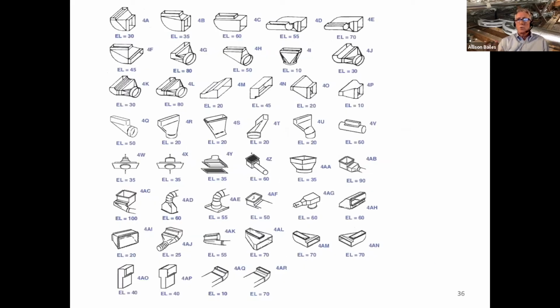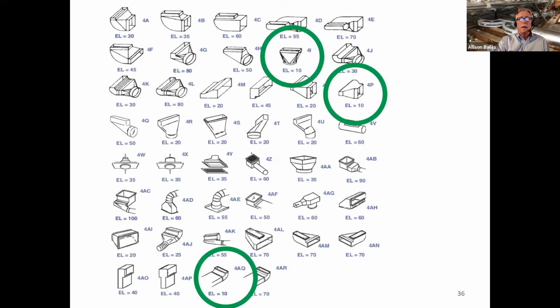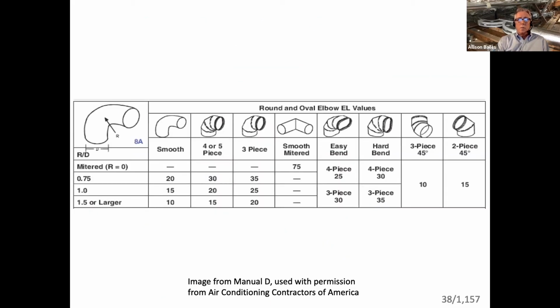And here are boots. Boots are the transition piece between a duct run and where the vent is in the room. And again, we've got some that are really low. We've got some 10-foot equivalent lengths here, and we've got a 90-foot. So if you want to do a low static air handler, you've got to pay attention to these numbers, and you want to go for the good fittings. Here are some elbows, and again, it depends on what kind of elbow it is and what the ratio is of the radius of curvature to the diameter of the duct.